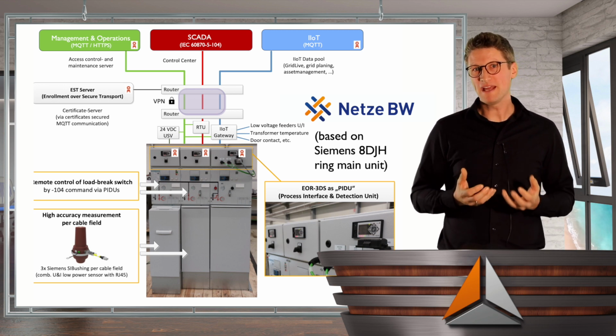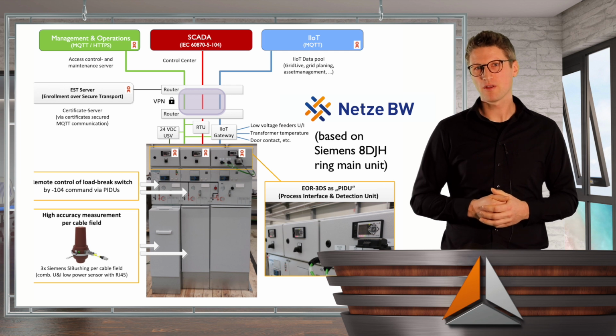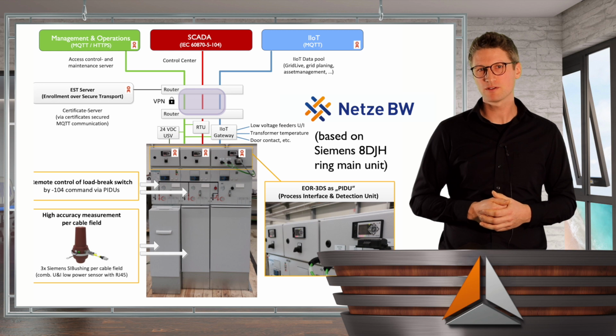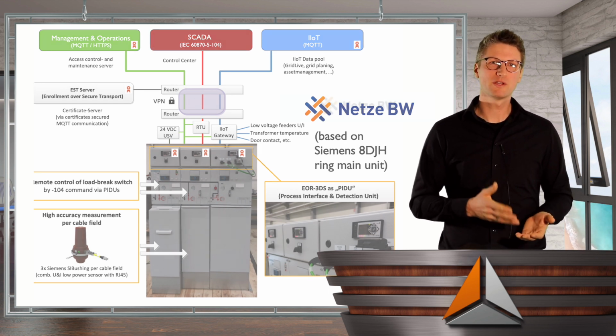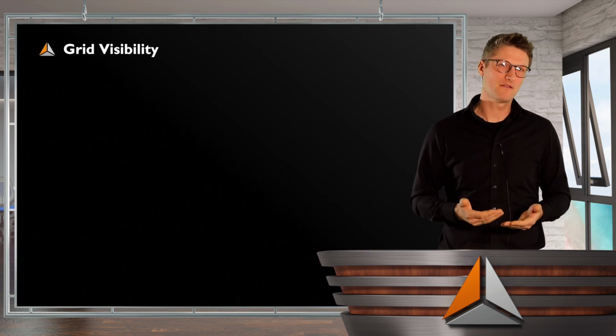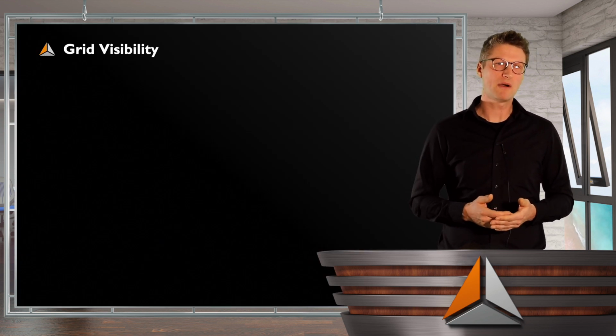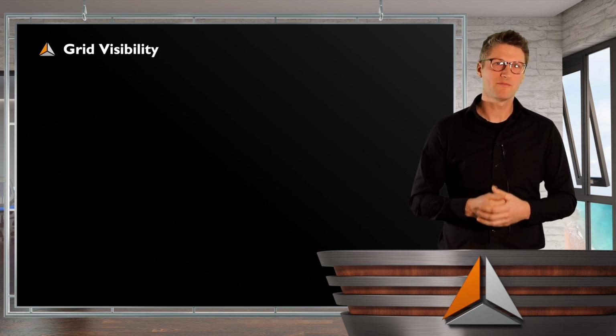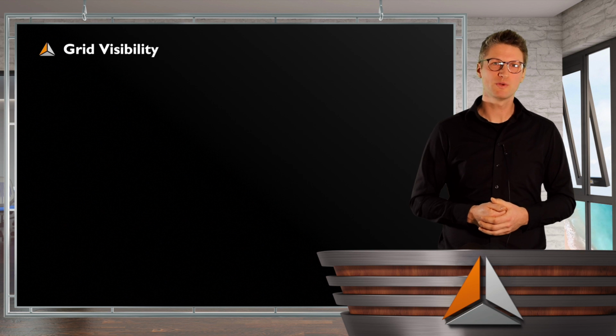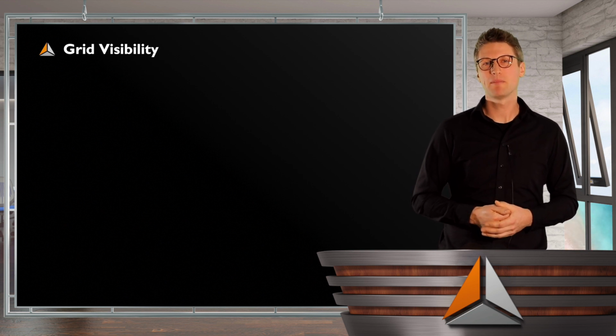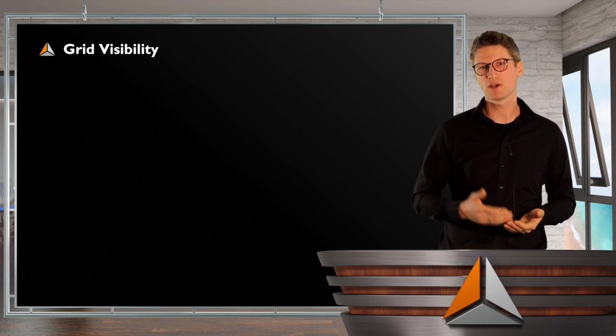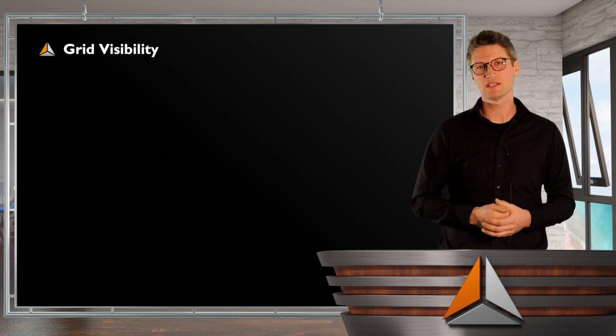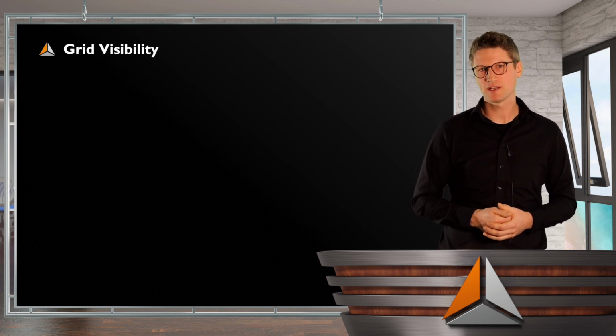Yeah, in the end, what is the benefit for the customer, for the DSO, to install these digital secondary substations? I want to mention especially 3 main topics. On the one hand, grid visibility. With these very accurate low power sensors of class 0.5, you get very accurate medium voltage readings in the central SCADA system, but not only in the central SCADA system, you get these values also via IoT for other departments like asset management or network planning.